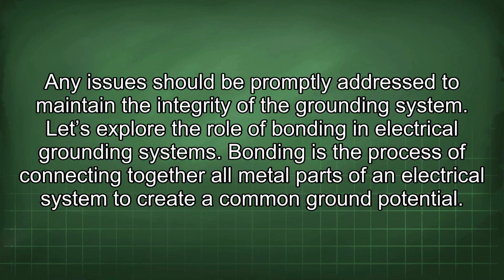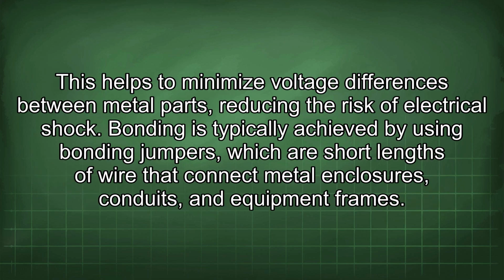Let's explore the role of bonding in electrical grounding systems. Bonding is the process of connecting together all metal parts of an electrical system to create a common ground potential. This helps to minimize voltage differences between metal parts, reducing the risk of electrical shock. Bonding is typically achieved by using bonding jumpers, which are short lengths of wire that connect metal enclosures, conduits, and equipment frames.